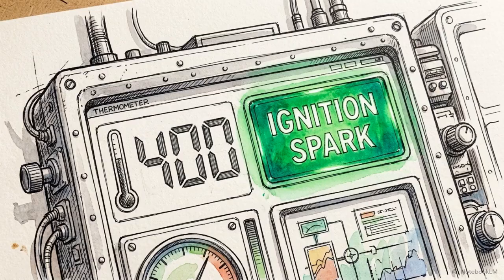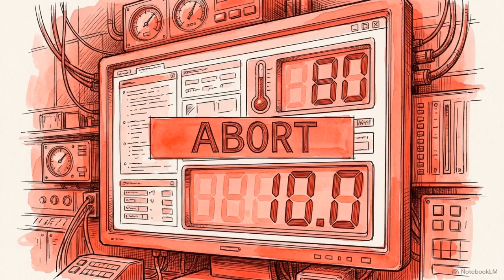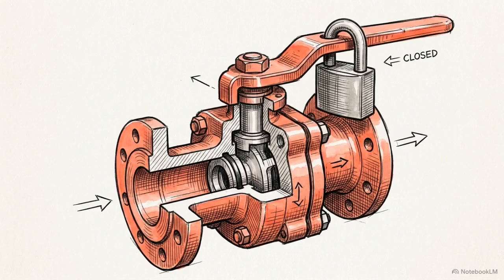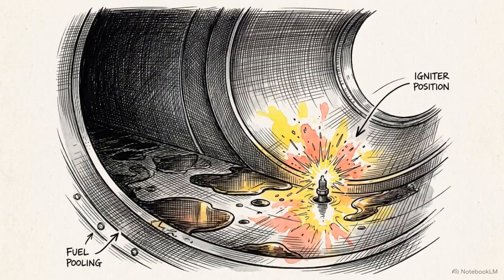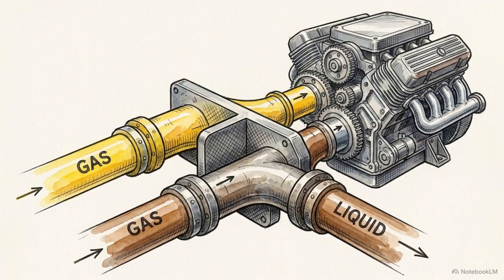Once the igniter sparks and fuel flows, the system monitors the exhaust temperature. If a rapid temperature rise isn't detected within a strict 10-second window, the start sequence aborts automatically. This abort is a critical safety measure. Pumping unburned fuel into a hot, pressurized combustor without a confirmed flame creates a severe explosive risk if ignition happens late. The engine is designed with a dual-fuel manifold, but it cannot run on a blend of both.